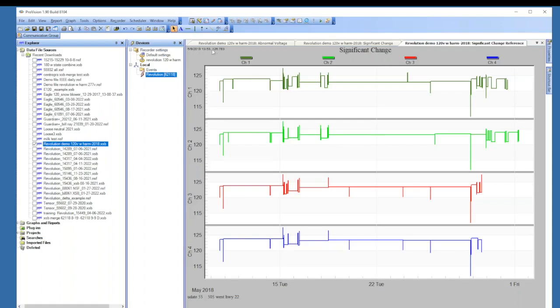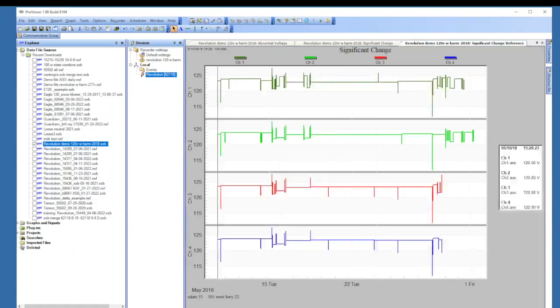So up here this tracks your cursor. So if you put a cursor, say right there, it will give you the voltage of 116.4 and also the time that occurred. So if we go over here, let's go down to, you can see we have a 112 there. Now there is a toggle point table that you can use also, and I'll show that later on too, but right click and select toggle point table, or just hit your T key. Your T key will toggle that in and out. And then if you put your cursor there, you can see what those are. And in this case, like I said, it's not a linear, so it's going to change depending on where that event is.